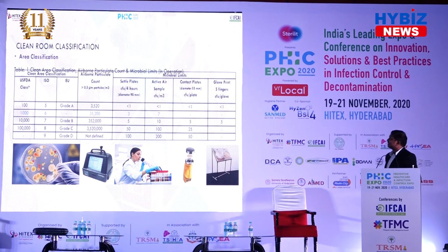These clean rooms, as I said in the previous slide, are designed as per the particulate counts and microbial limits. Other than temperature, RH and differential pressure, the critical parameters that define the clean room are the airborne particulate count and the microbial limits.